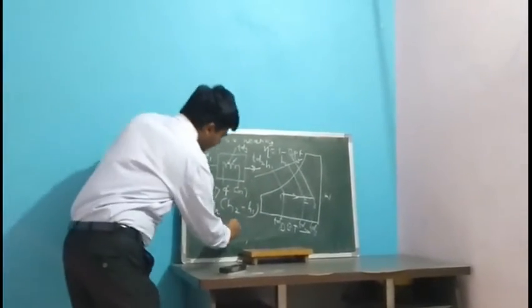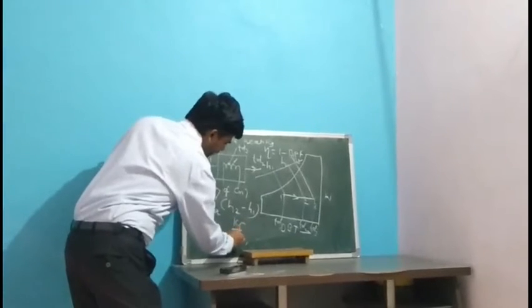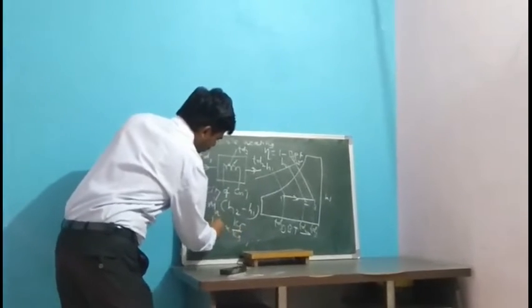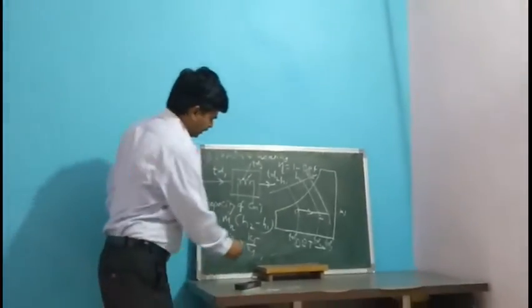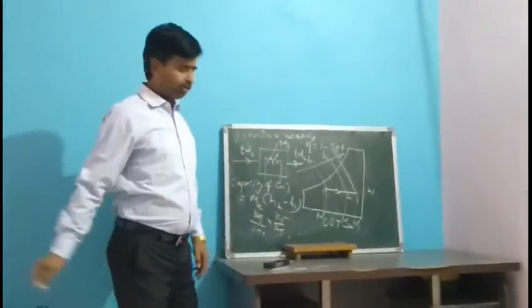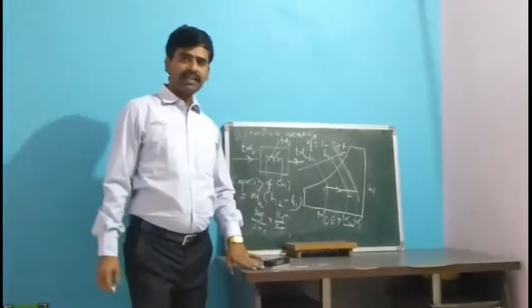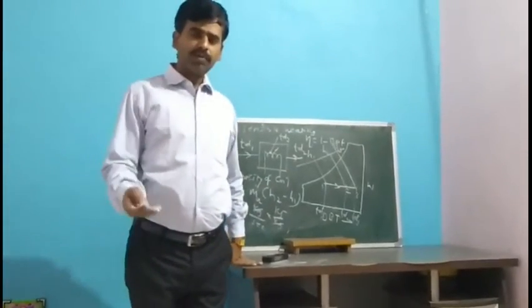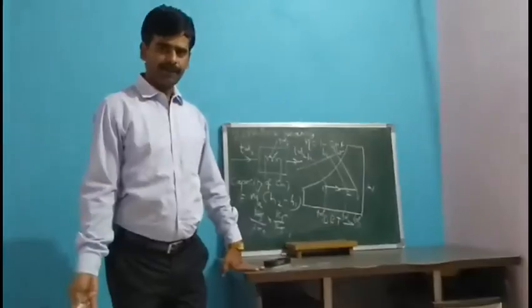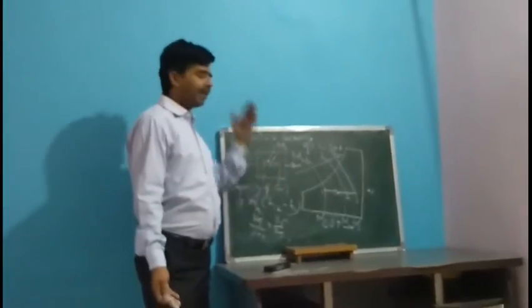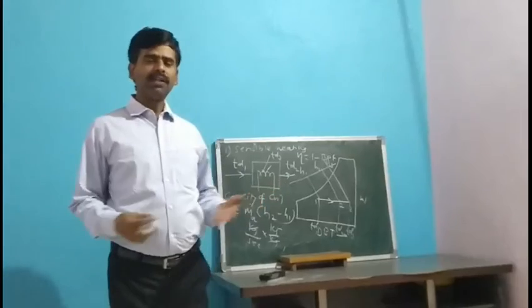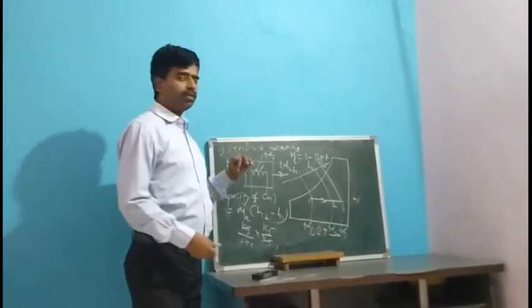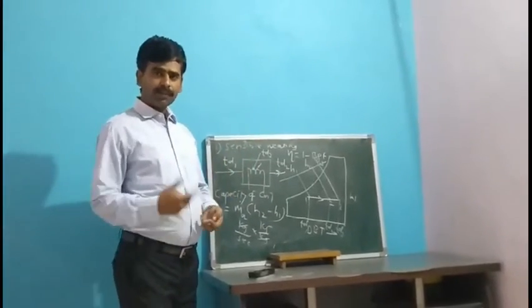The enthalpy is in kilojoule per kg and the mass flow rate of air is in kg per second, so the kg will cancel out. We get kilojoule per second, and kilojoule per second is known as a kilowatt. So in this way we can determine the capacity or wattage of the coil that is needed for this particular process.